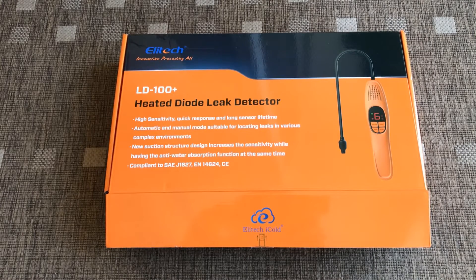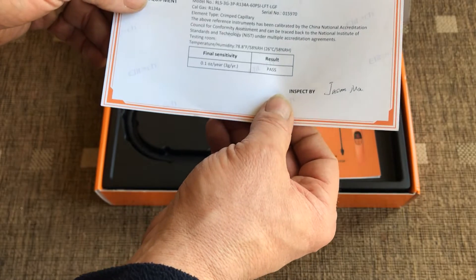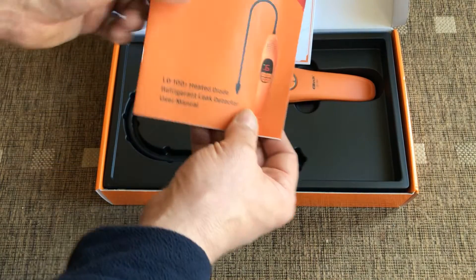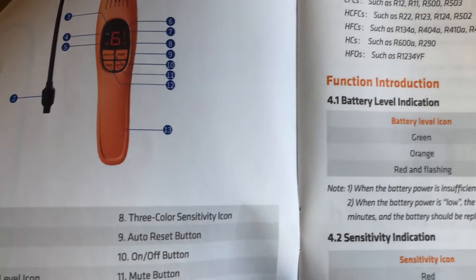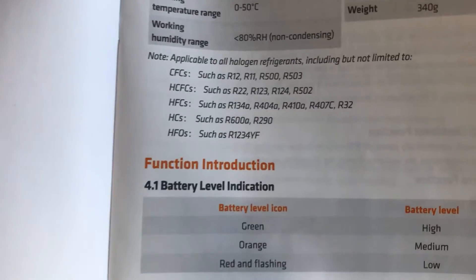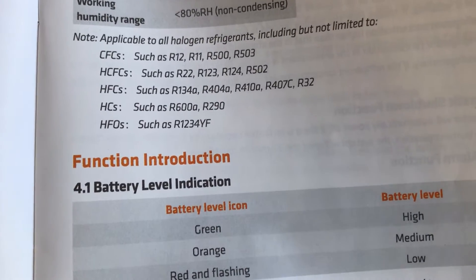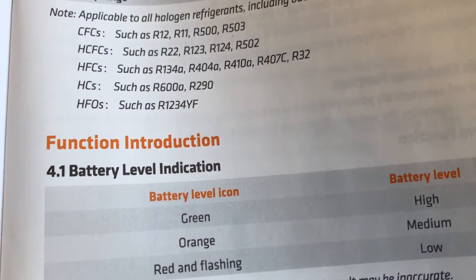Hi there, Carlos here. Welcome — I'm here today to give you a review on the Elitech LD100 Plus. This is a heated diode leak detector and Elitech claim this will do hydrocarbons and all refrigerants. In the box we have a performance report claiming sensitivity of three grams per year, so it's up with the rest of the models on the market. We also have an instruction pamphlet — Elitech instruction pamphlets are very detailed and easy to follow. I'm particularly interested in hydrocarbons, as we're seeing more R600a and R290 in the industry, and I'm keen to see how it performs.